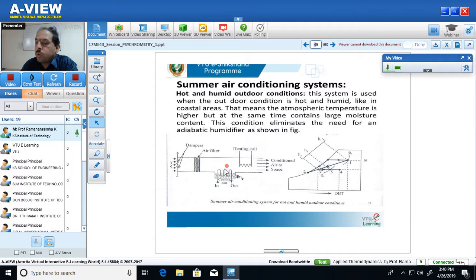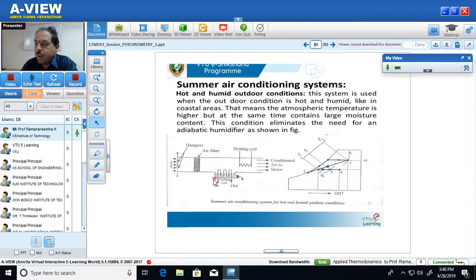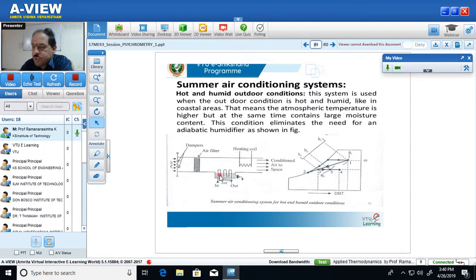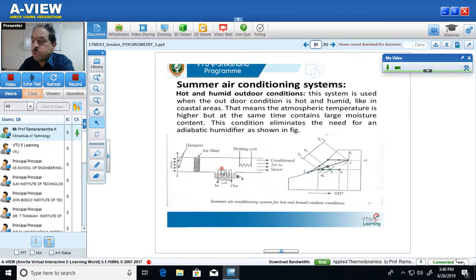First, the air rejects heat to the cooling coil, causing the temperature of air to decrease. In addition, since the air is already humid and has excess water vapors, those excess water vapors are removed and collected in the well or container. So how to represent this on the psychrometric chart? Two things are happening: it is a cooling process, and during cooling the temperature decreases. Since excess water particles are removed, the humidity level also decreases.